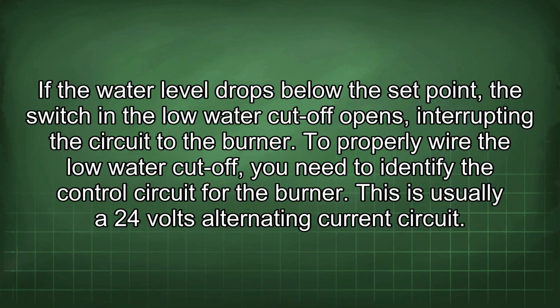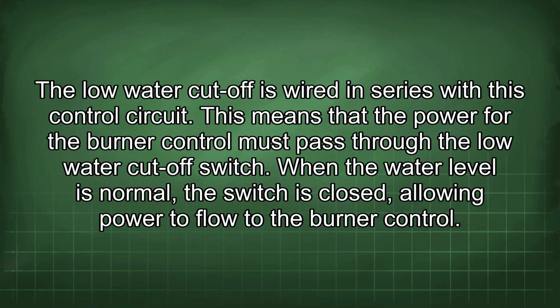If the water level drops below the set point, the switch in the low water cutoff opens, interrupting the circuit to the burner. To properly wire the low water cutoff, you need to identify the control circuit for the burner. This is usually a 24 volts alternating current circuit. The low water cutoff is wired in series with this control circuit. This means that the power for the burner control must pass through the low water cut-off switch.